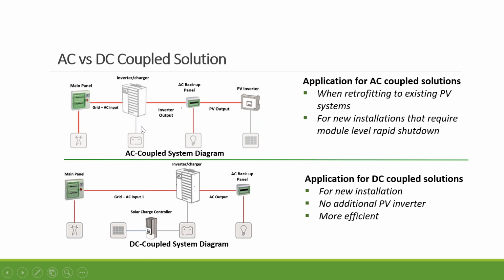Now, the battery is really being charged by the hybrid inverter, which takes the power either from the PV or from the grid. So that's why it's called AC coupled. So it's on the AC side. The AC coupled solution is mainly used when you look to retrofit to an existing PV array, especially if you have microinverters or optimizers that are almost impossible for you to go back and take off. And AC coupled works well.